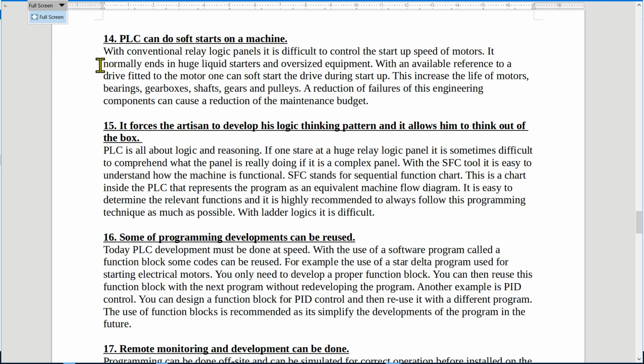Now, with an available reference to a drive fitted to the motor from the PLC, one can actually soft start the drive during startup. In other words, we can give it a speed reference, and it will start slowly and then start to accelerate or decelerate as needed. Today, even your drive has acceleration and deceleration speeds built into the circuit. And your PLC can interface very easily with these, and they actually complement each other.